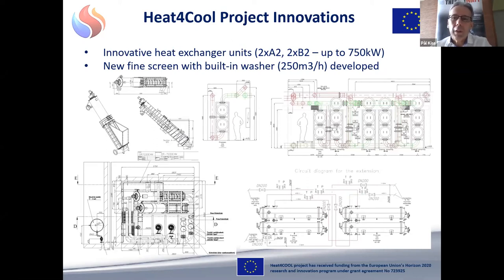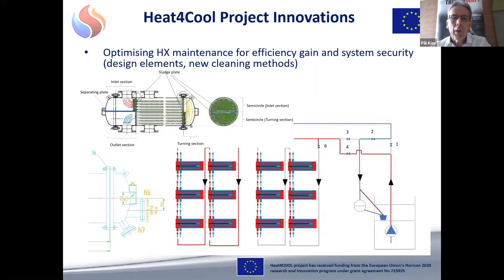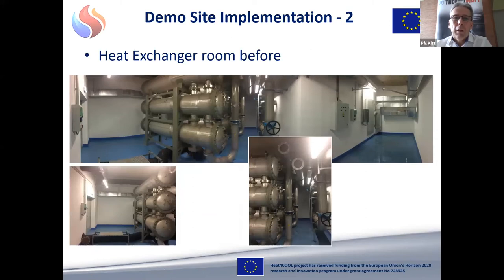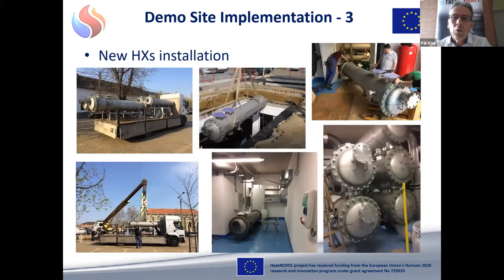So here we use different types of inlets. We use reverse flows, and we also work on the size of the tubes, because those are tube and shell type heat exchangers. Here are some pictures of the inlet part and the outlet part of the heat exchanger that we modified compared to others, and we monitor on site. Here you see the place where we put in the new heat exchangers. And those are already the new heat exchangers developed by us.